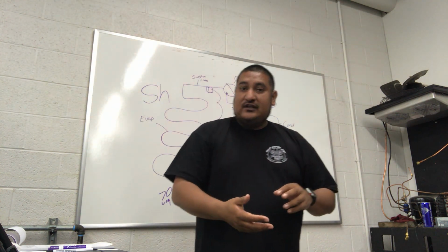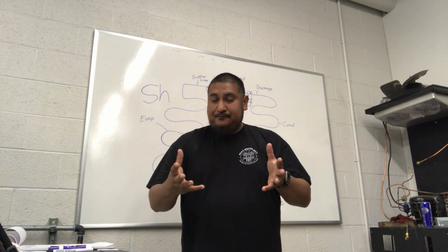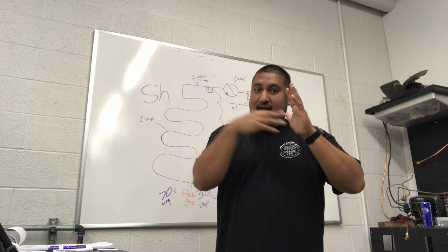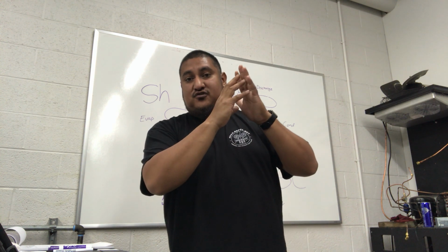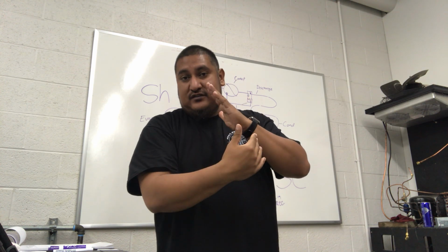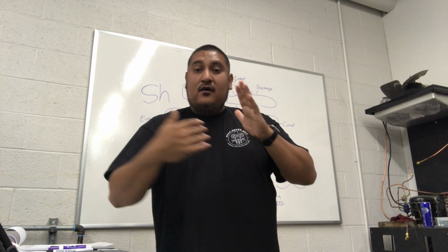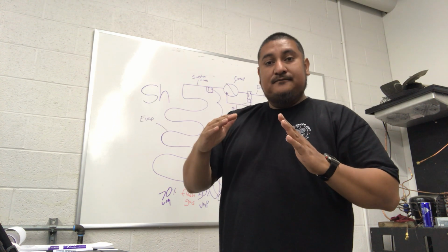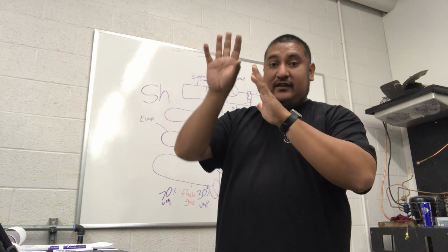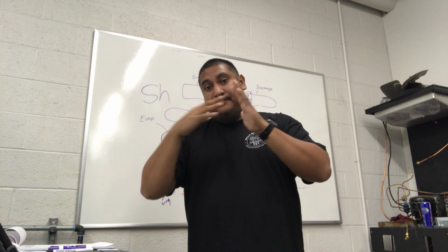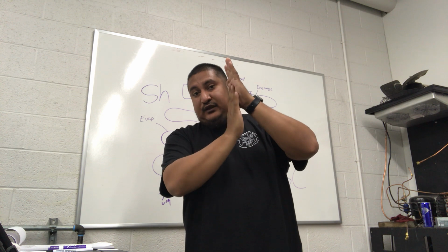The evaporator is no different. The evaporator is cold, and you've got warm air rushing up against it. So what's going to happen? That hot air is going to give off its moisture to that cold evaporator, and you're going to have condensation. You're going to have water running down this evaporator. Well, if we have a refrigerant that's at or below 32 degrees, we're going to freeze that water on the evaporator. That will actually cause an air restriction, because we're building ice here.